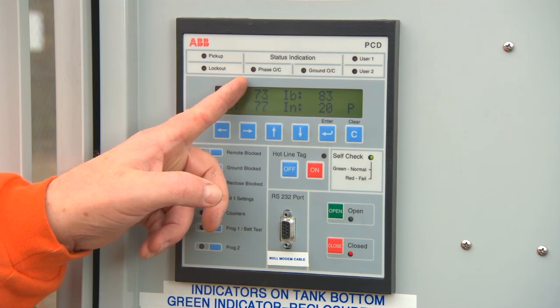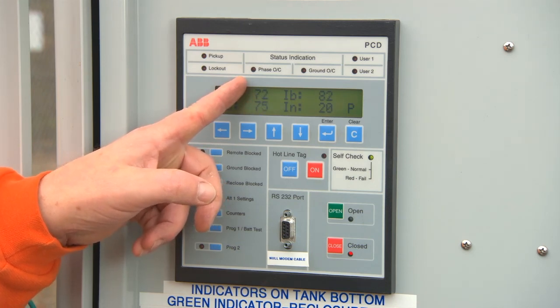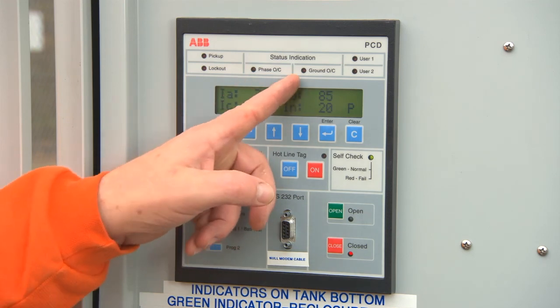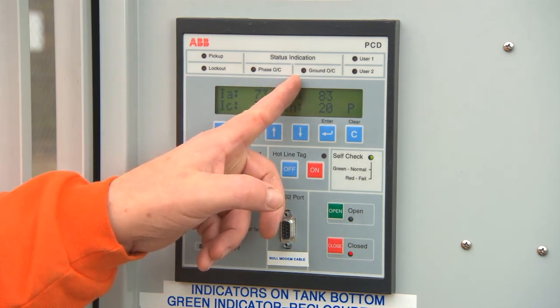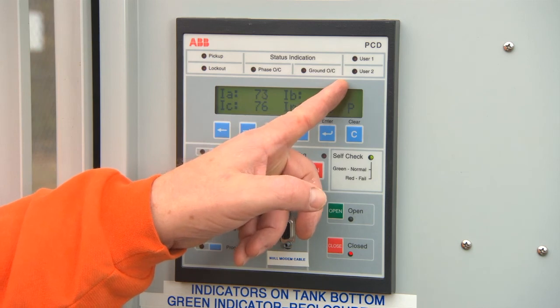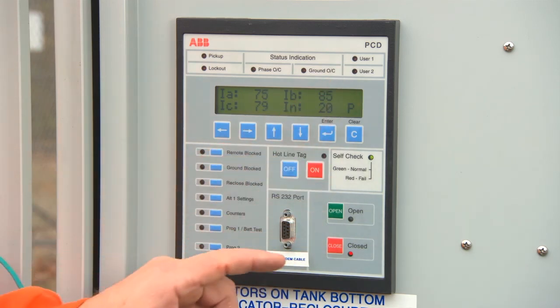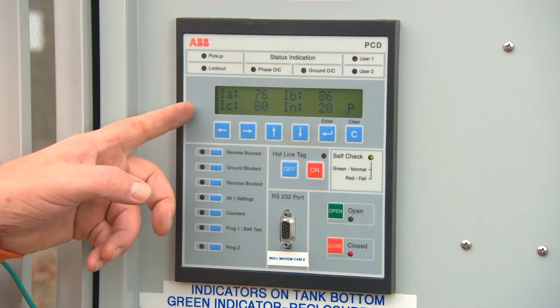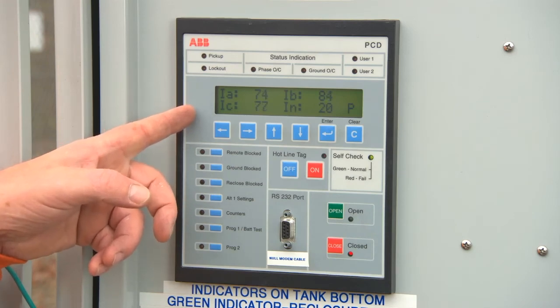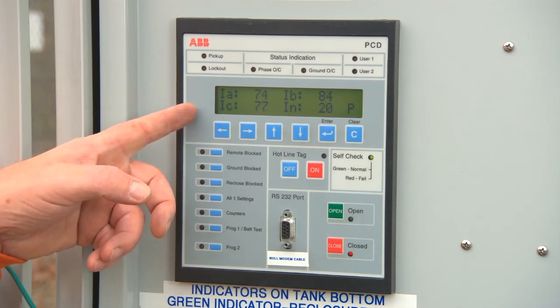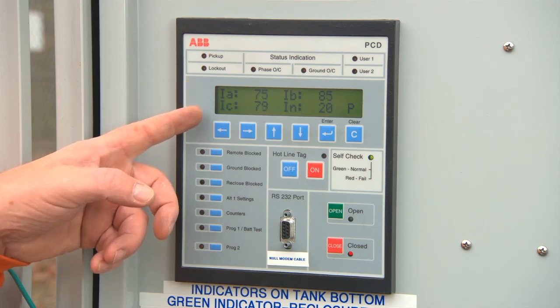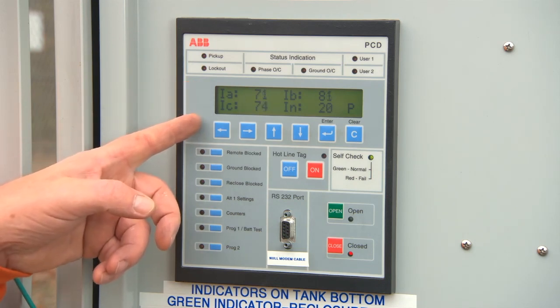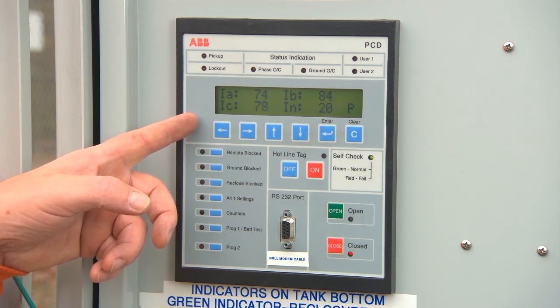Phase overcurrent. This LED will turn red upon a phase overcurrent trip. Ground overcurrent. This will turn red upon a ground overcurrent trip. User 1 and 2 are only used when you are connected to the control. The default display screen will show the actual current flow through each individual phase, A, B, and C, in addition to the IN, which is your calculated imbalance or neutral.